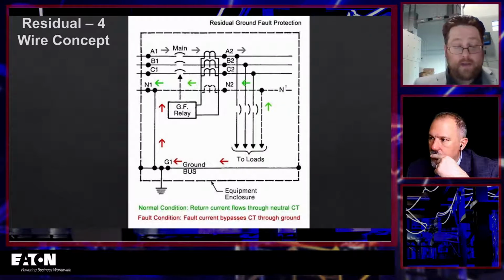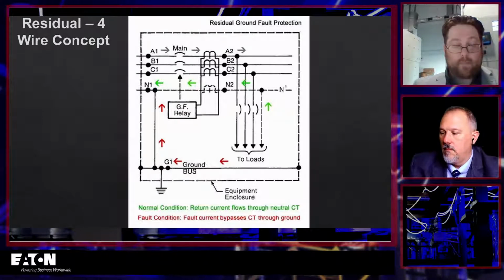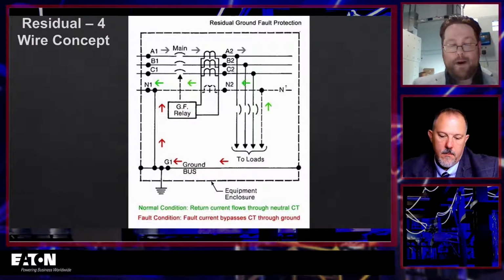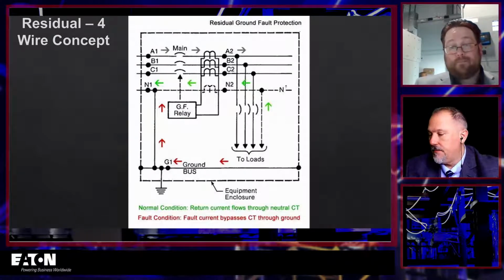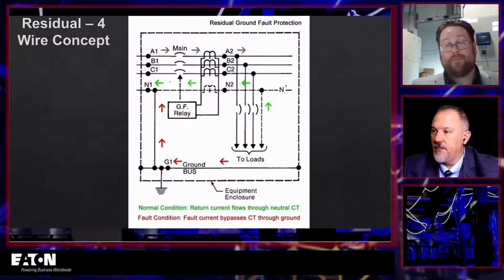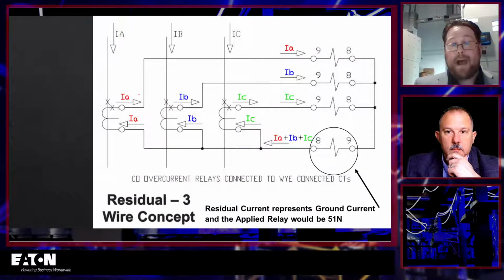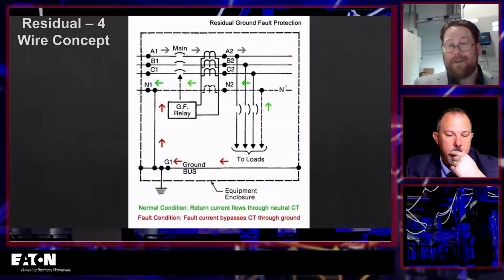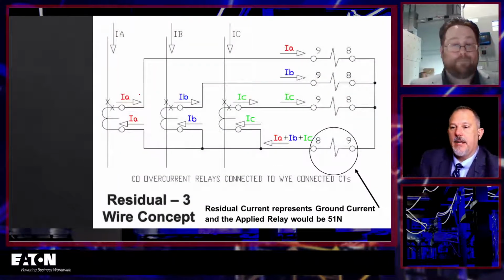Right. Yeah. And actually, when we talk about Eaton's Magnum DS, if you purchase a 4-pole breaker, you can do residual grounding where every pole of the breaker, all 4 of them, would have the sensors, right? The CTs installed into it, and it's all wired, it's all internal to the breaker. You don't have to worry about all that external wiring if you do that. That's right. Yeah, and that's very convenient. Very convenient. But ultimately, the math is the same. It's just doing a summation of all of the currents, and it should add up to be 0. That's right. I'm liking it.